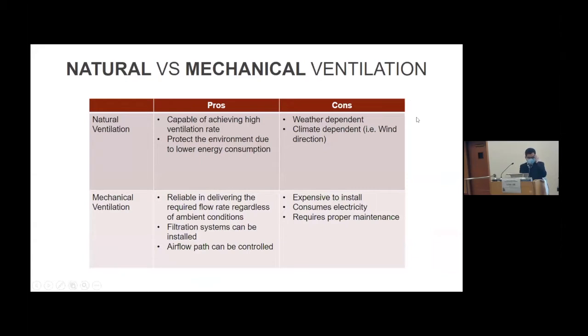As one can imagine, natural ventilation is free of charge and capable of achieving high ventilation rates. Since it does not need electricity to operate fans as compared to mechanical ventilation, energy consumption is relatively lower, or even zero. On the cons side, natural ventilation depends heavily on the weather condition and wind direction. In humid places like Hong Kong, we rarely see buildings that use natural ventilation.